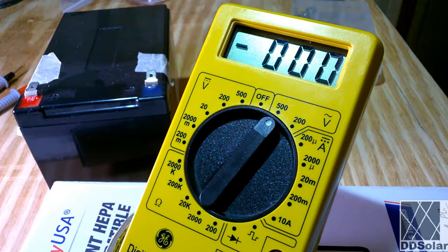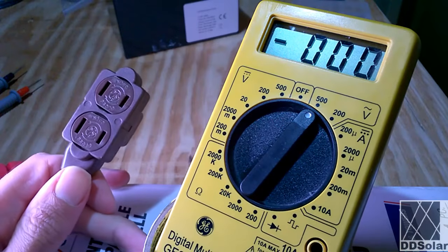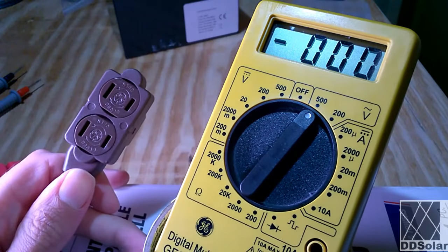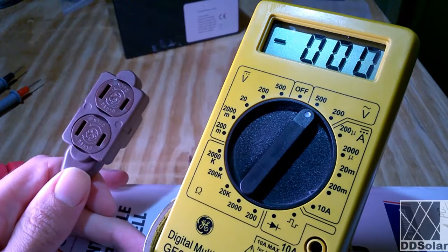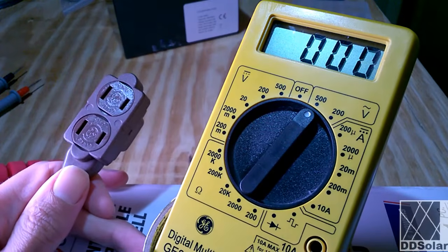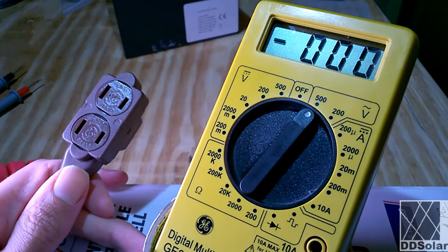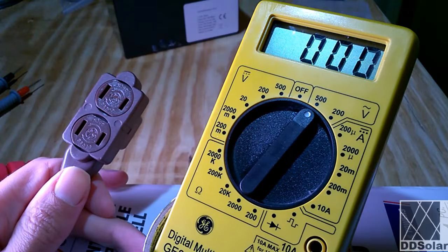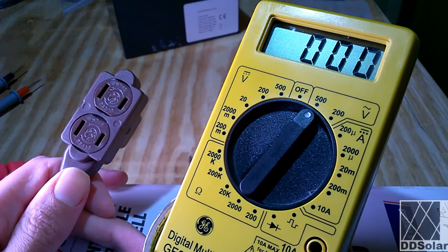I'm going to do something on camera that is probably ill-advised for most beginners. Nevertheless, I'm going to show you how it's done. Here's a pretty typical AC power cord on the left here. It is live, it is plugged into the wall. There is going to be a time where you might want to measure a cord like this to see if there is any voltage coming out at all. So I'm going to show you how I do it, and this is generally dangerous if you don't know what you're doing. Now before I take this voltage measurement, can you think of something that you should always check on the meter before doing this?